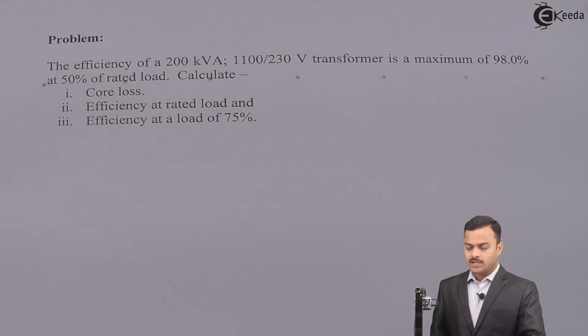So here is the problem. The efficiency of 200 kVA 1100/230 volt transformer is a maximum of 98% at 50% of the rated load. Calculate core loss, efficiency at rated load and efficiency at a load of 75%. So let's solve it.